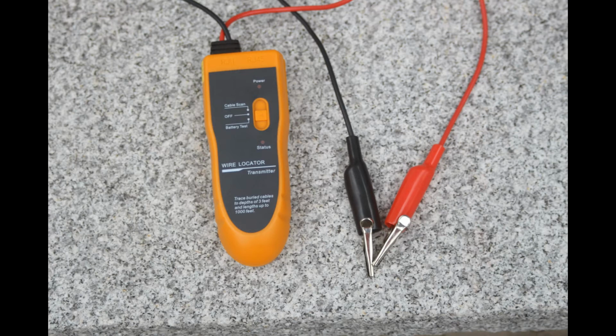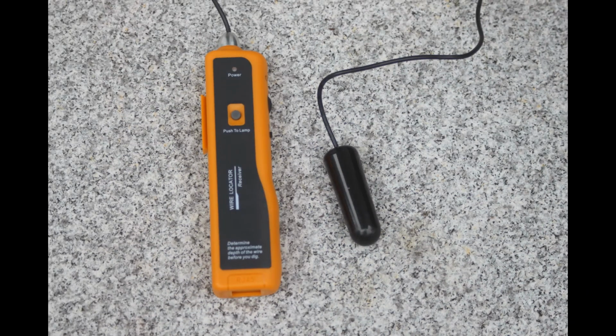Now, this is the transmitter. It's got a battery tester on it, and when you switch the switch to the other position, it transmits a signal. You have the two alligator clips. As I said earlier, I pulled open the outlet and exposed the wires. I was able to clip onto the black and white wire on the 220 line in the outlet and turn the transmitter on. So now I was set to move on to the next phase.